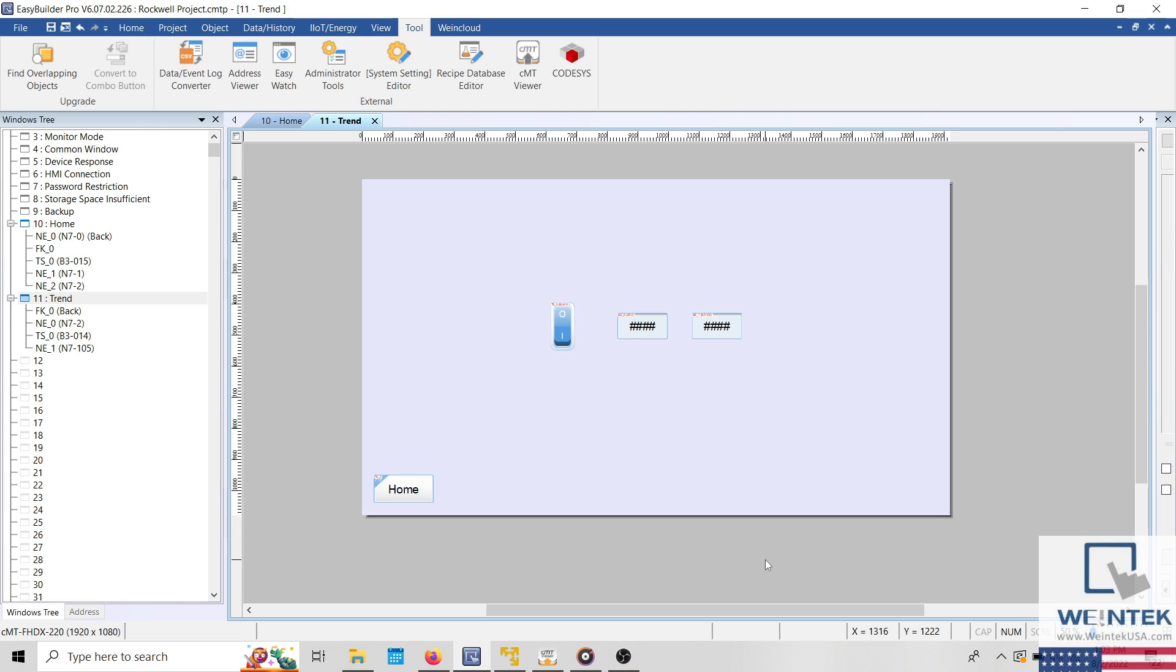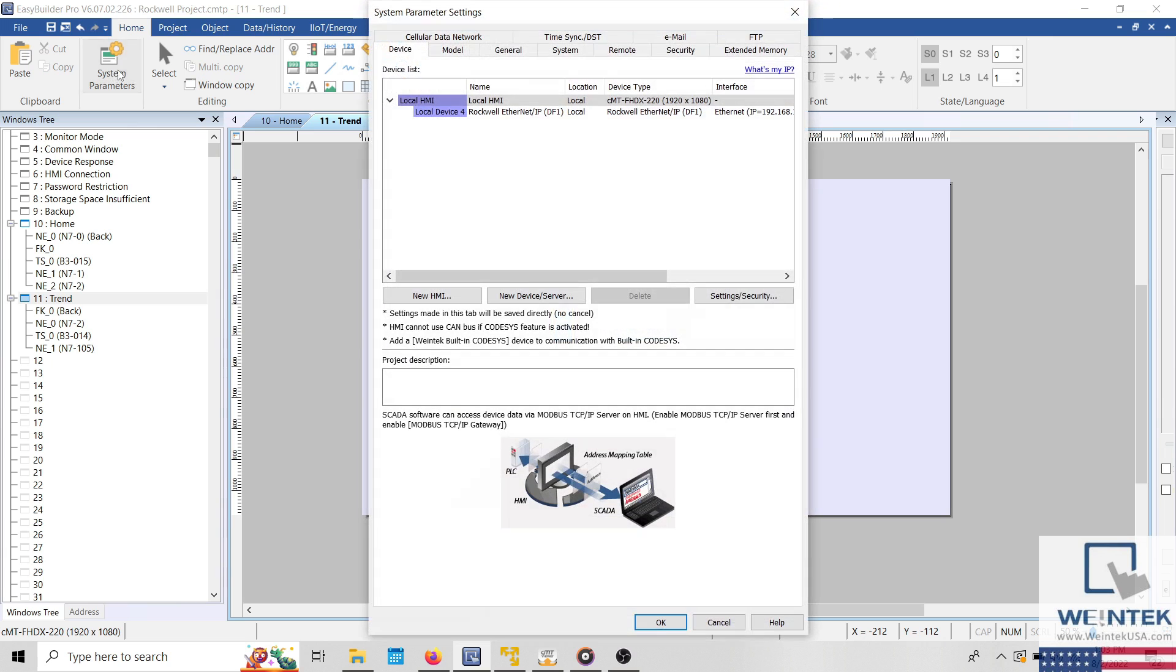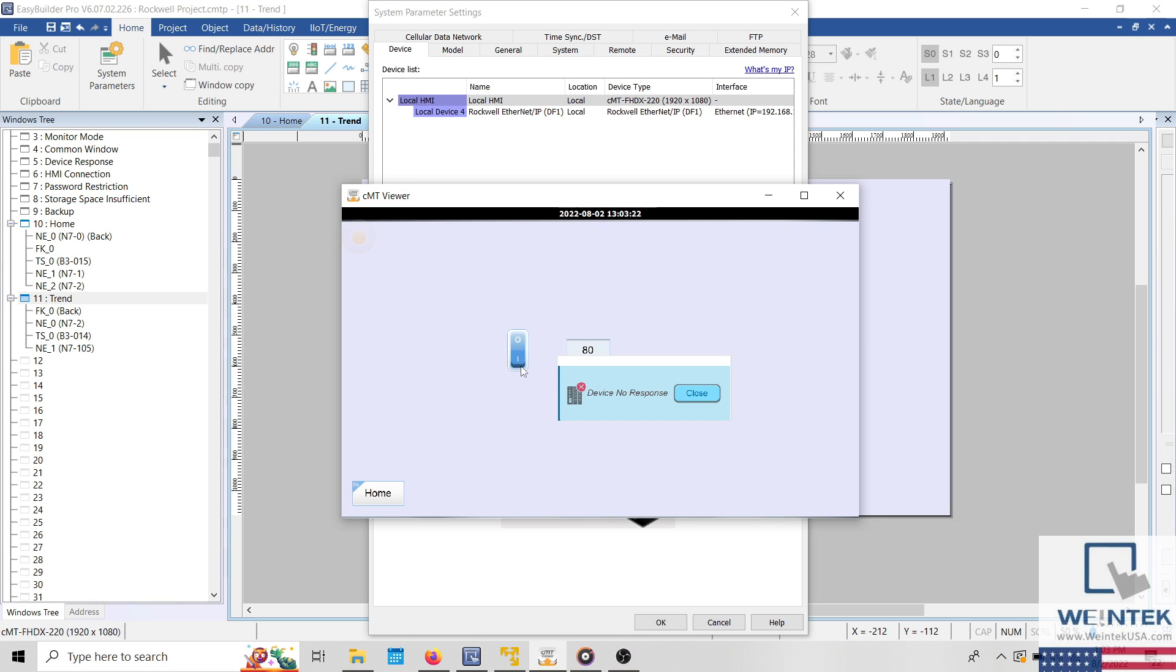To begin, I have a simple project on display that was designed to allow my CMT FHDX to communicate with a MicroLogix 1100. However, when monitoring this project using CMT Viewer, the HMI displayed a device no response message. This message can be both frustrating and confusing when it seems that the HMI can communicate with the PLC seemingly without issue.